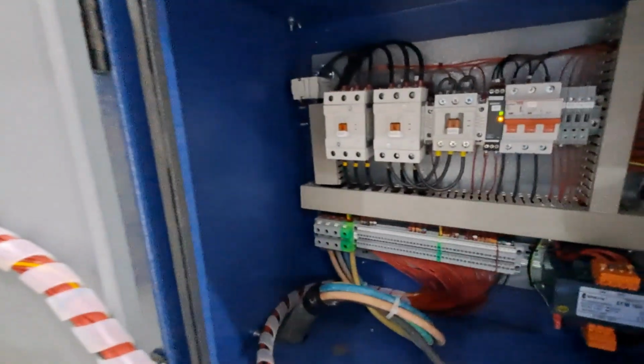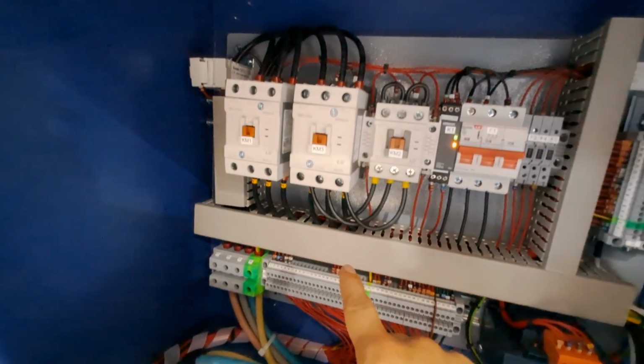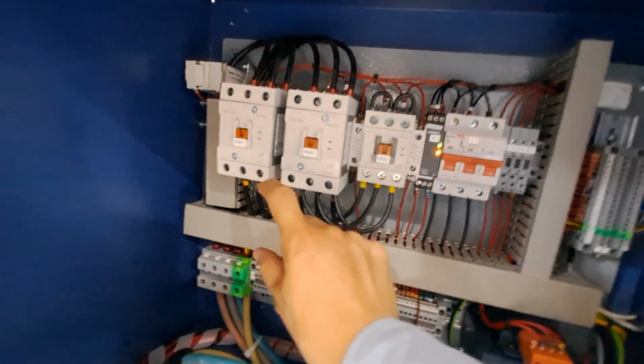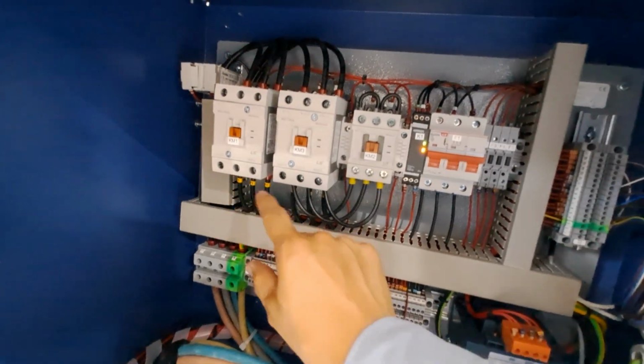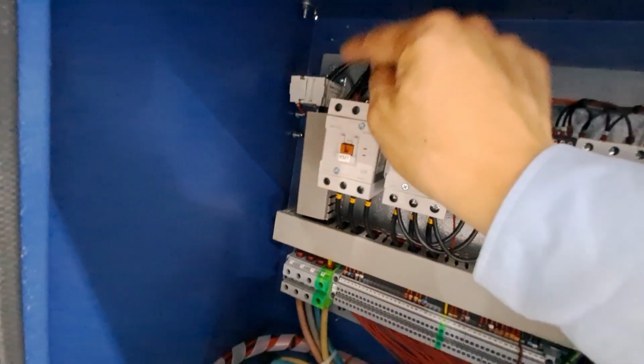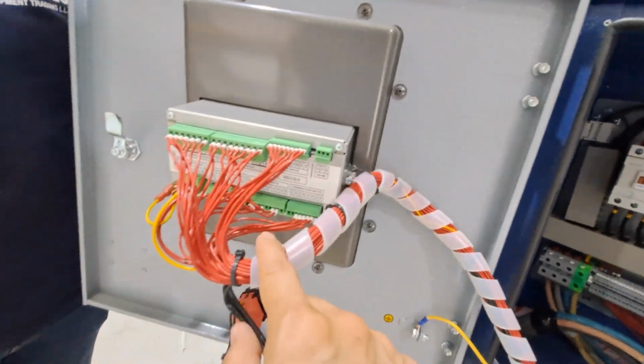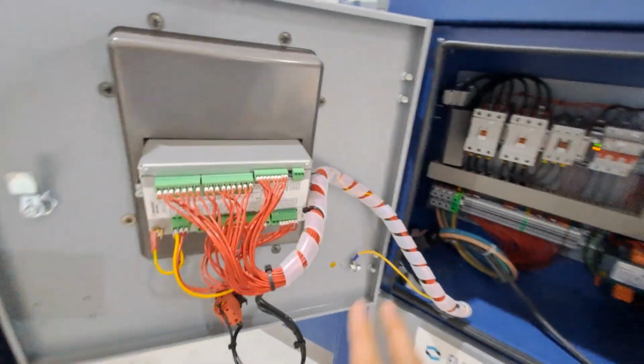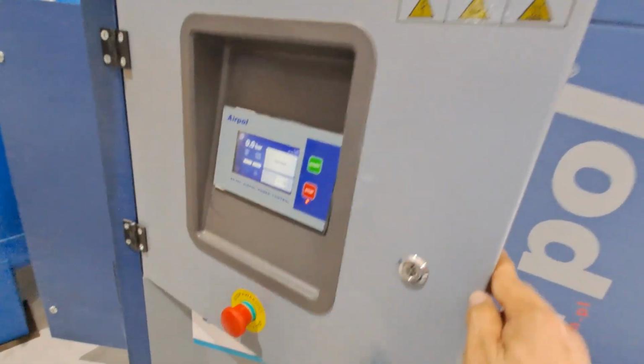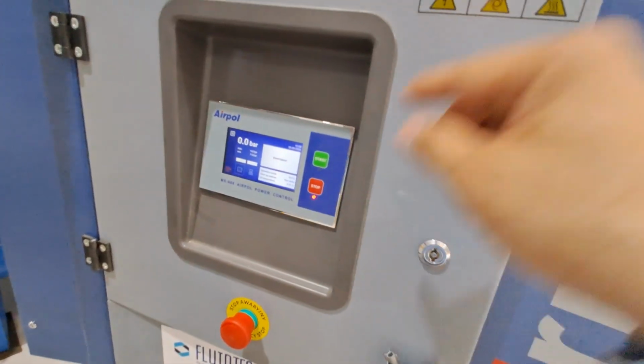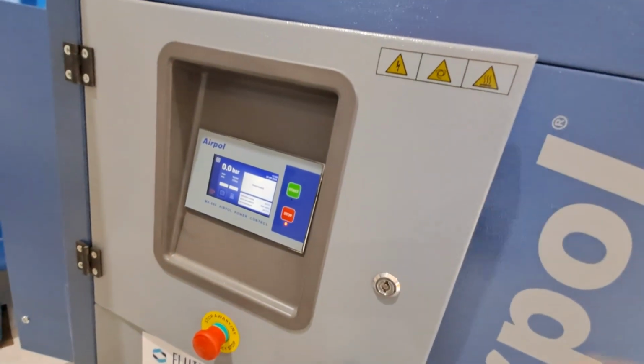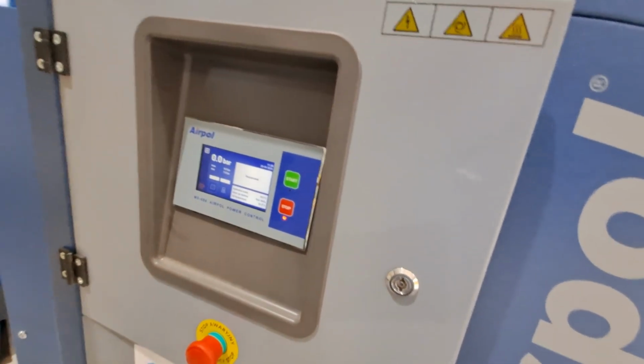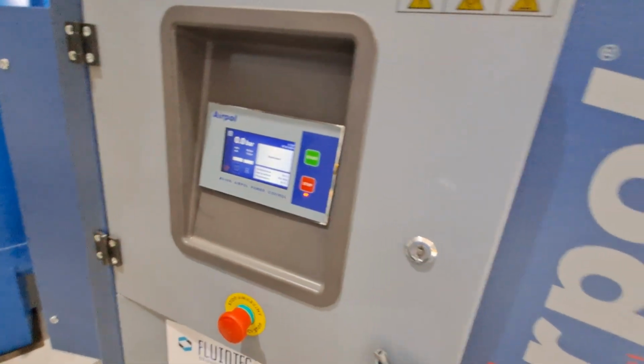Okay, so as you see here, just for clarification, the motor doesn't have an overload relay or overload contactor. It is safely cut off through the current transformer. There is a CT coil here, an ampere meter, which intelligently works: if the controller senses high current flowing into the line, the controller will turn off the supply or the contactor. Now Engineer Muhammad will explain to you about the controller.